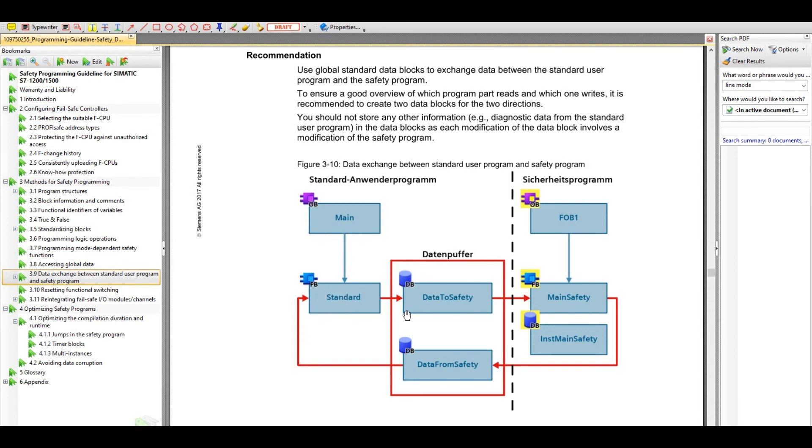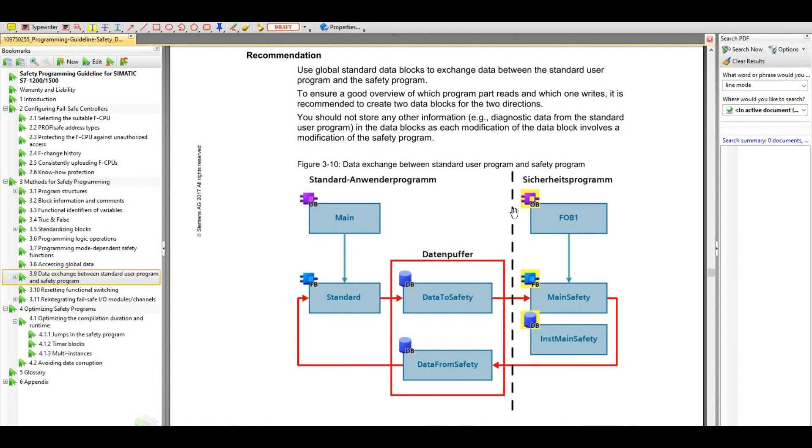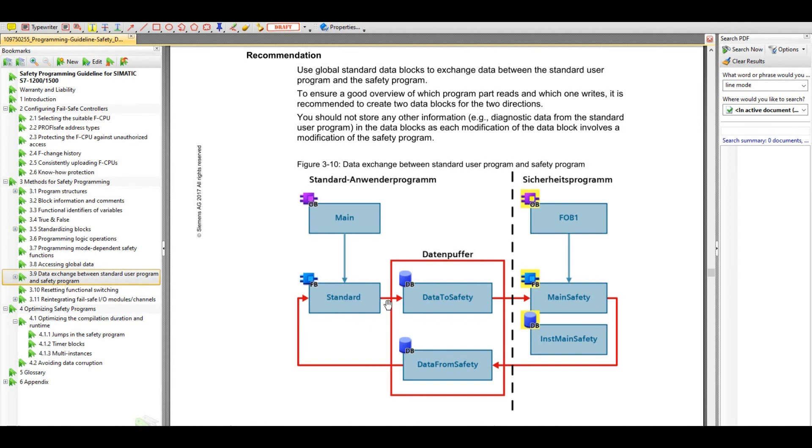With this interface DB, even if you change something in this standard DB, but if there's no change on the interface DB, no recompile, no add one line in this interface DB, for this area from the safety view, there will be no any change in this area, even if your standard logic changed or DB changed. That is one key idea. We need to use the buffer DB here.